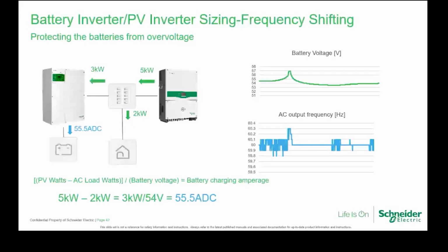So you've got to make sure that you look at your load profile and see if you've got enough charging capability from the PV inverter size, so that it's got enough available current for the XW to charge those batteries, if you want to use those batteries at night time as well. So it's a bit of give and take, where you look at your load requirements, look at what the generation capability is, and make sure you have enough energy to charge those batteries during the day.